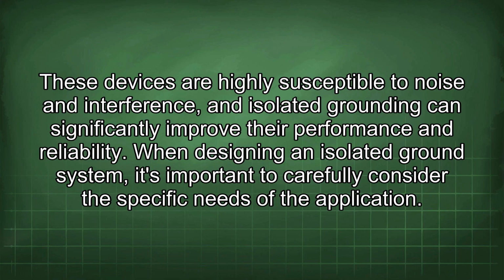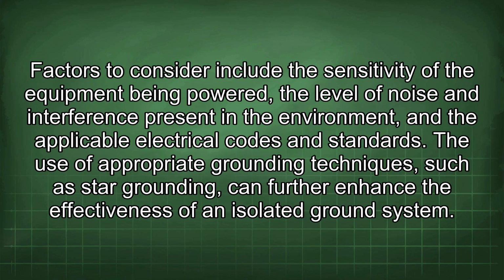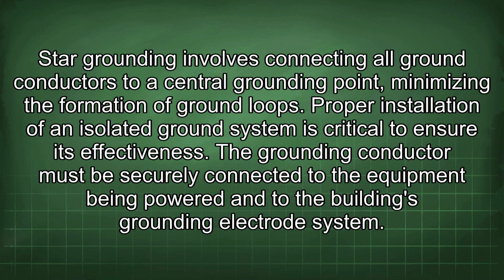When designing an isolated ground system, it's important to carefully consider the specific needs of the application. Factors to consider include the sensitivity of the equipment being powered, the level of noise and interference present in the environment, and the applicable electrical codes and standards. The use of appropriate grounding techniques, such as star grounding, can further enhance the effectiveness of an isolated ground system. Star grounding involves connecting all ground conductors to a central grounding point, minimizing the formation of ground loops.